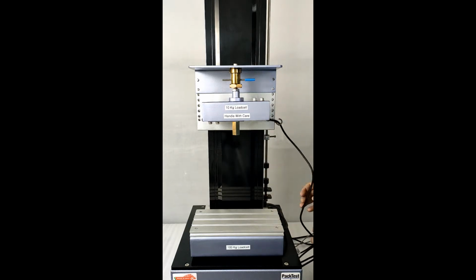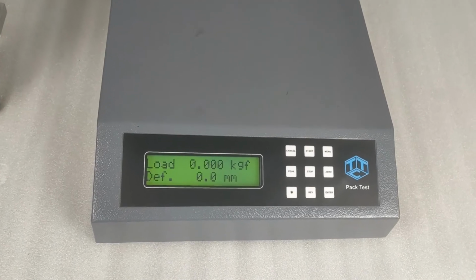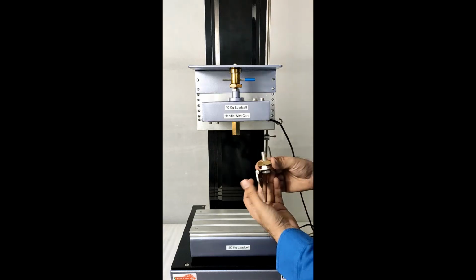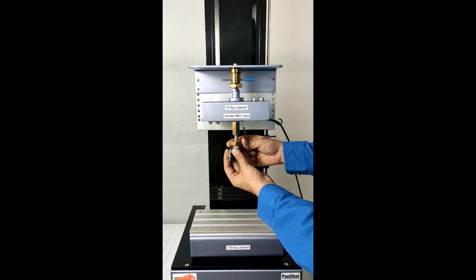Connect the load cell cable to the controller of the machine. Switch on the controller. The machine will auto-detect the connected load cell, and the screen will now look like this. Now attach the flip opening fixture as shown.